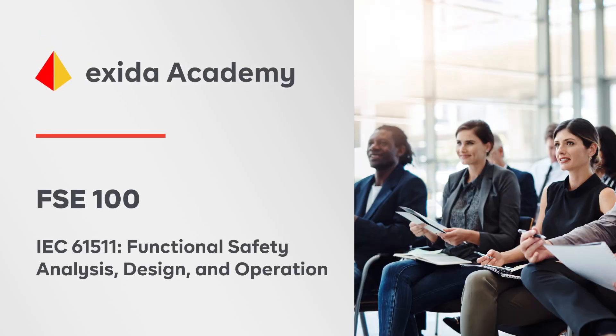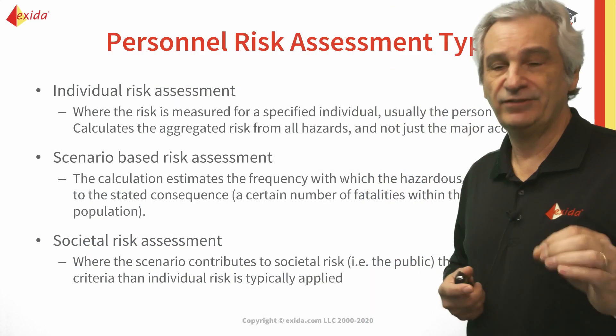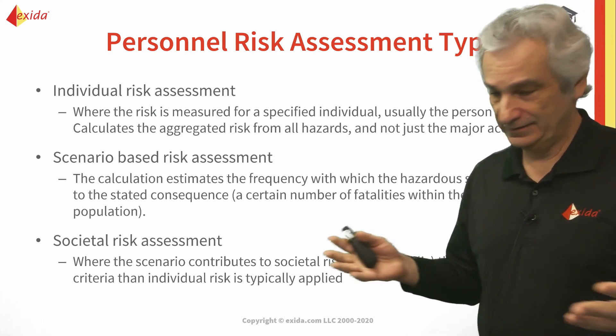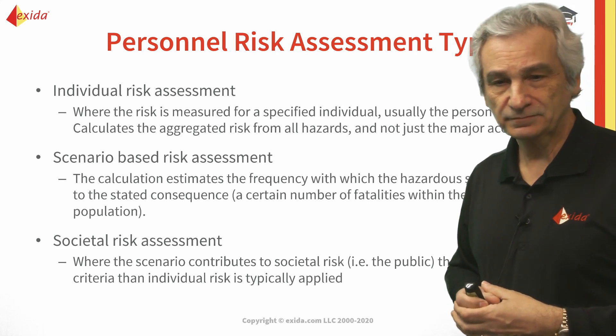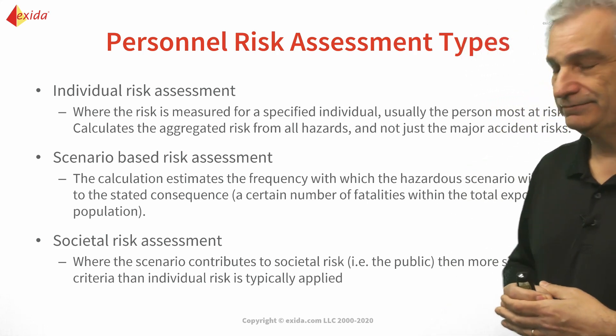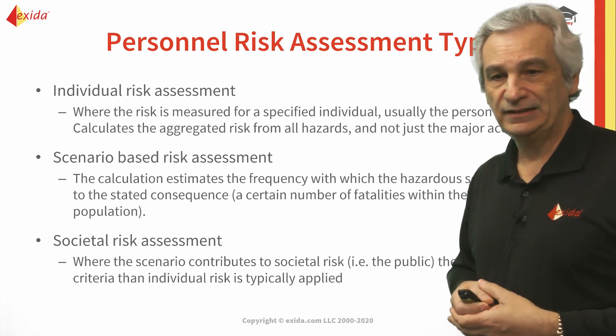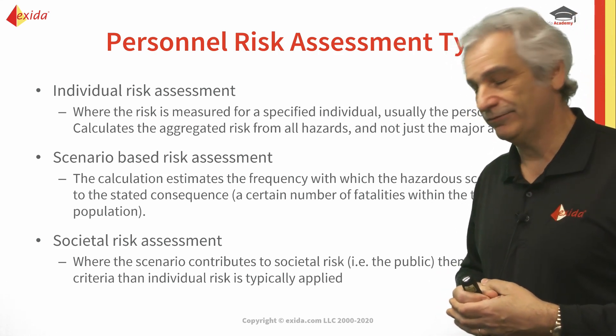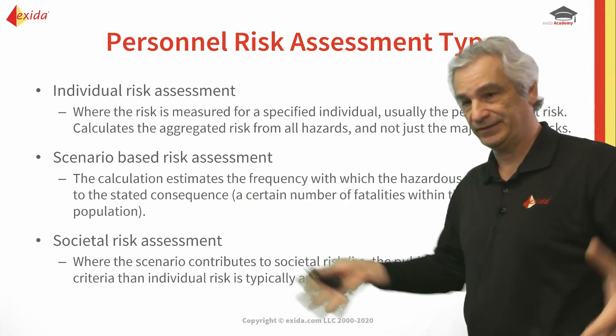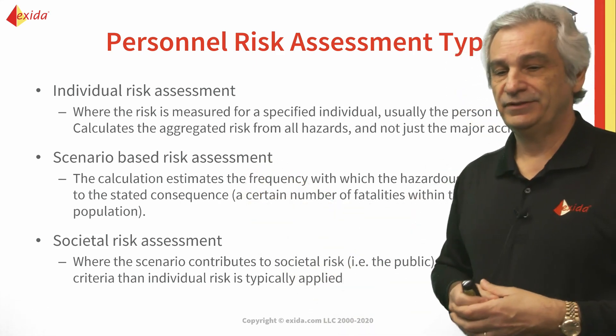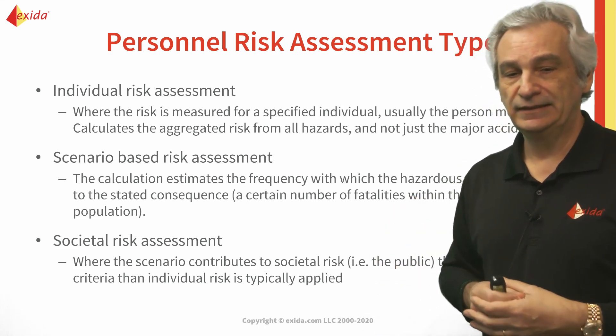When looking at personnel risk assessment types, we can look at individual risk, where the risk is measured for the specific individual — usually the maintenance or operations person out in the field who is most exposed. Then we look at scenario risk, examining the frequency with which a hazardous scenario will occur and the consequences in terms of potential fatalities for a given population. Societal risk is where this contributes to risk that goes beyond the plant fences. We want to minimize the time our plant people spend in exposed or potentially dangerous areas.